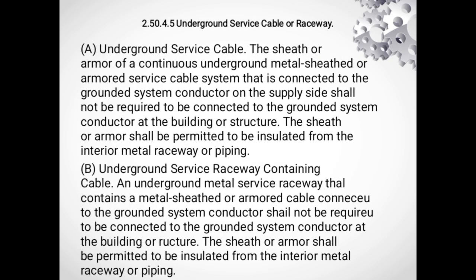2.50.4.5 Underground service cable or raceway. A. Underground service cable. The sheath or armor of the continuous underground metal sheathed or armored service cable system that is connected to the grounded system conductor on the supply side shall not be required to be connected to the grounded system conductor at the building or structure. The sheath or armor shall be permitted to be insulated from the interior metal raceway or pipe. B. Underground service raceway containing cable. An underground metal service raceway that contains a metal-sheathed or armored cable connected to the grounded system conductor shall not be required to be connected to the grounded system conductor at the building or structure. The sheath or armor shall be permitted to be insulated from the interior metal raceway or piping.